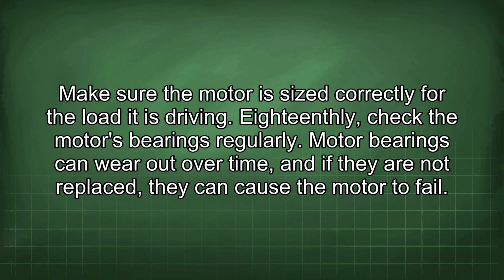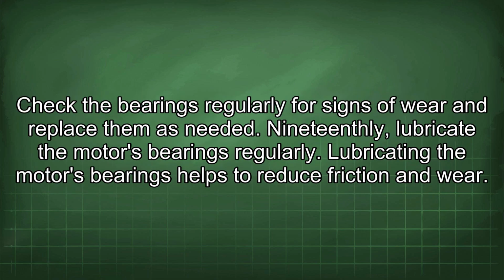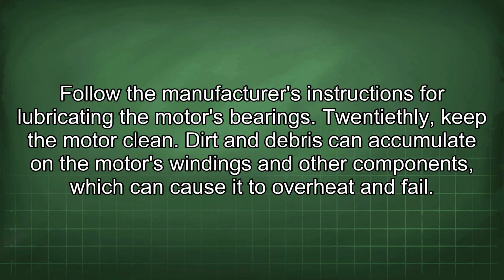18thly, check the motor's bearings regularly. Motor bearings can wear out over time, and if they are not replaced, they can cause the motor to fail. Check the bearings regularly for signs of wear and replace them as needed. 19thly, lubricate the motor's bearings regularly. Lubricating the motor's bearings helps to reduce friction and wear. Follow the manufacturer's instructions for lubricating the motor's bearings.